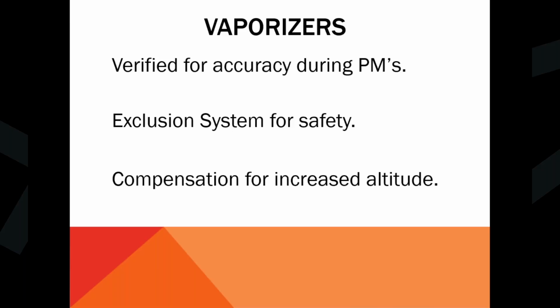Some of the older machines, which you probably won't run into anymore, had an external exclusion system and could have up to like 3 vaporizers on it. So you had to turn on and check each and every vaporizer and make sure the other 2 or 1 wouldn't come on at the same time. Like I said, it's a very complicated mechanical type system, but most of them are built in now. So you just try and turn the other one on while you have the one you're testing on. If you can't turn it on, then that checks your exclusion.